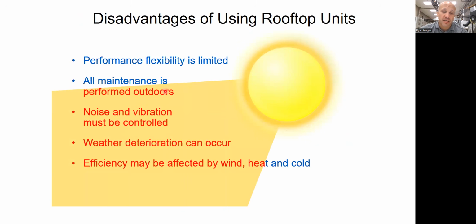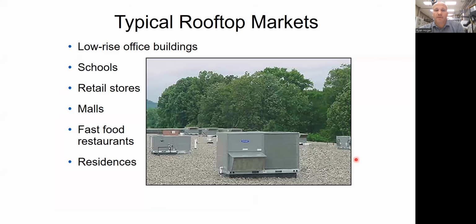All the service and maintenance is done outdoors, which doesn't sound bad until you realize it's super hot on a black tar roof, or it's raining or lightning or any of those things. You don't want any vibration from the unit to propagate its way through the roof, especially if you're putting this over a critical area. And then obviously everything being in the elements just makes it deteriorate a little bit faster than if you had half of the equipment inside, right? So common applications, like we said, strip malls, which are low-rise buildings, low-rise office buildings, sometimes schools, not always, but like maybe the office area at the school would have rooftops, whereas the classrooms might have unit ventilators or something like that. Fast food restaurants.